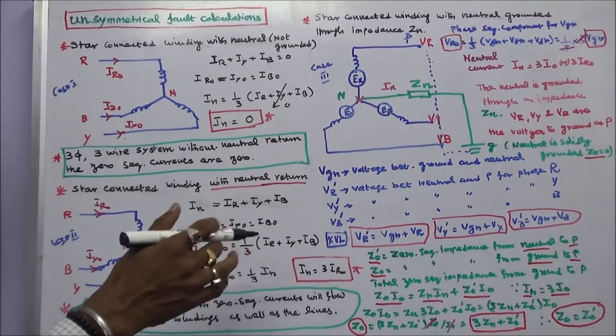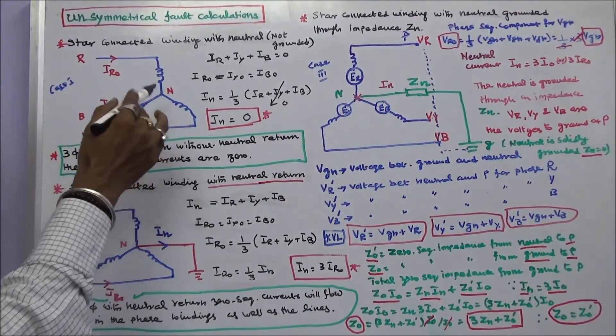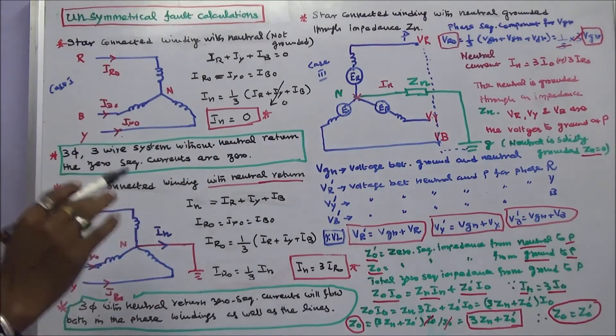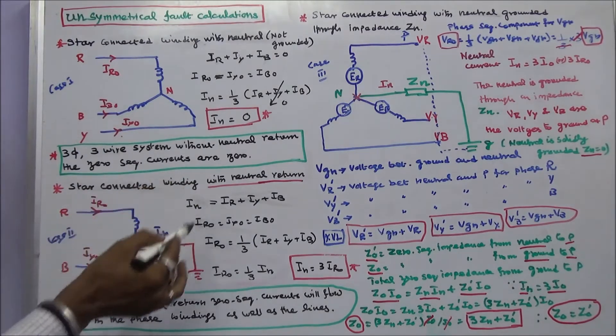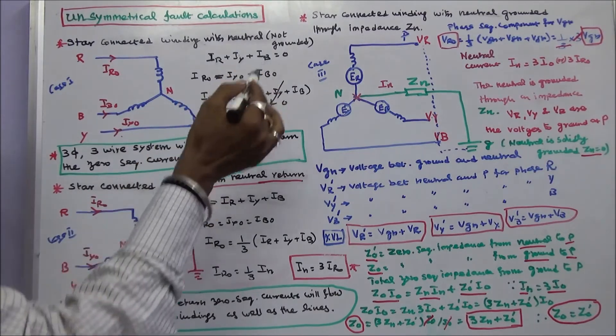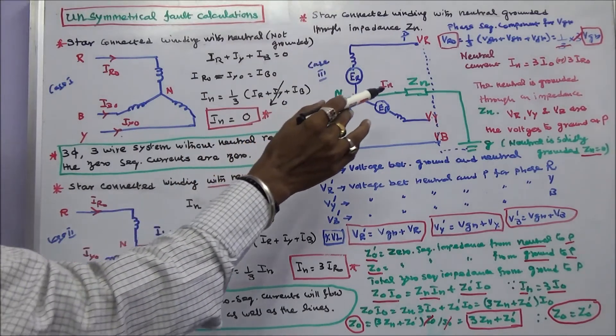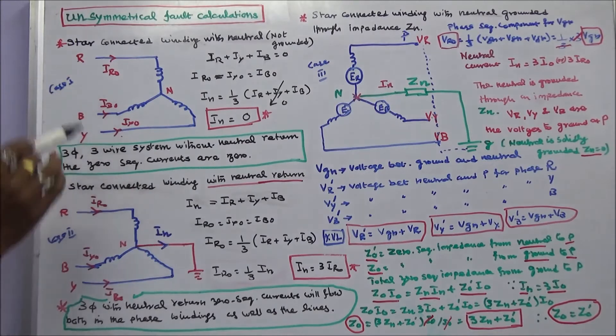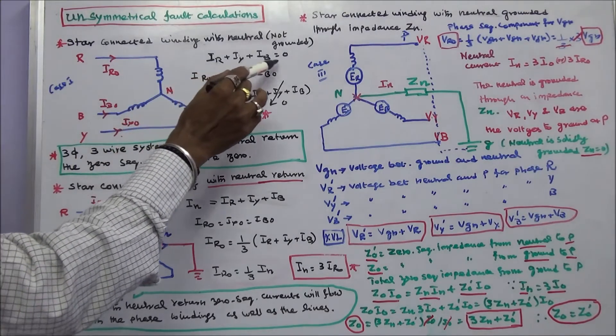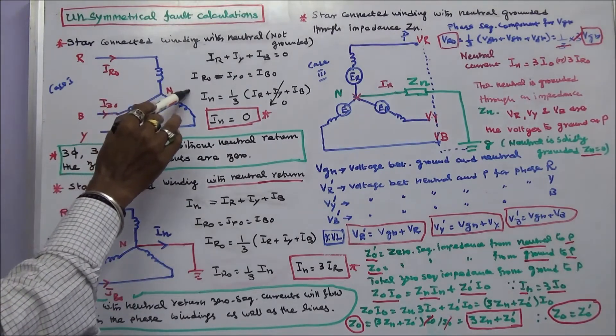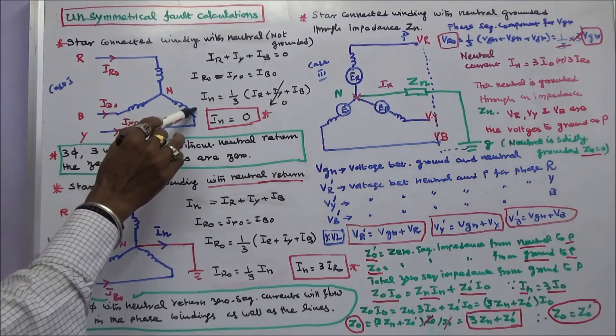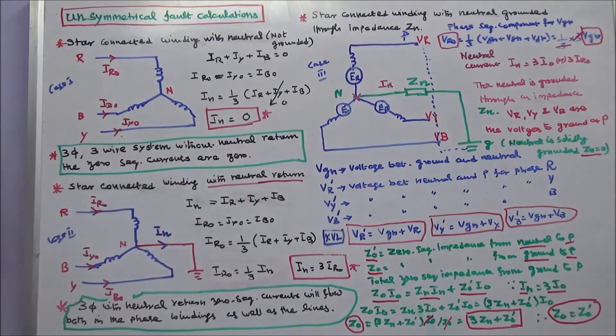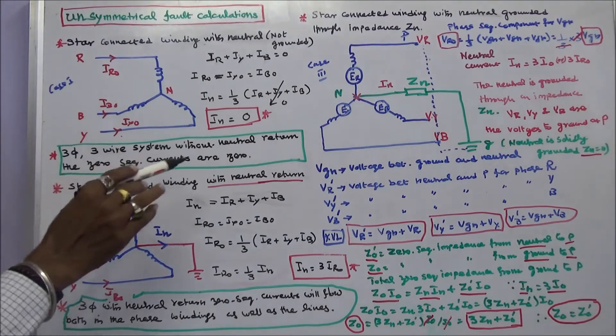Now we will discuss three cases. Case 1: star-connected winding with neutral not grounded. Here IR plus IY plus IB is equal to zero. The zero-sequence current IR0 equals IY0 equals IB0. Neutral current IN is equal to one-third times (IR plus IY plus IB). Since IR plus IY plus IB equals zero, the neutral current is equal to zero. In a three-phase three-wire system without a neutral wire, the zero-sequence currents are zero.